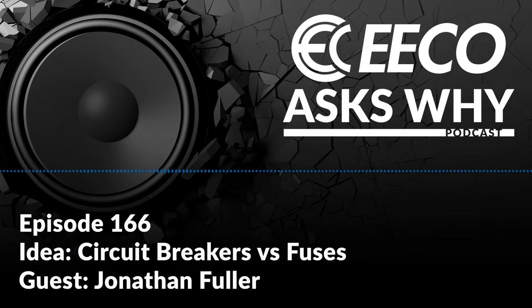And then with circuit breakers as well, you can have ground fault circuit breakers, you can have multi-pole circuit breakers for two phase, three phase power. You can have arc fault circuit breakers, and you can start getting into electronic trip units and things like that to be able to adjust the different ratings of that circuit breaker, so it might trip on 10 amps or it might trip on 15 amps, or the different short-term, instantaneous and long-time tripping characteristics. So with the circuit breaker, you can really dial into what you need in that circuit and adjust different characteristics to coordinate a system together. Whereas with fuses, you can't necessarily do that.